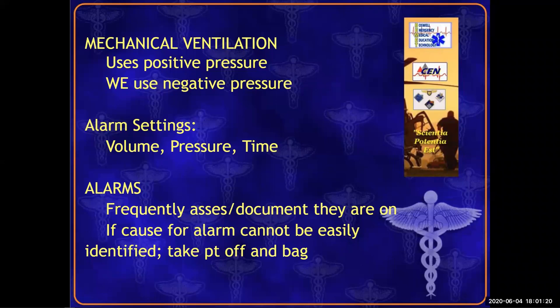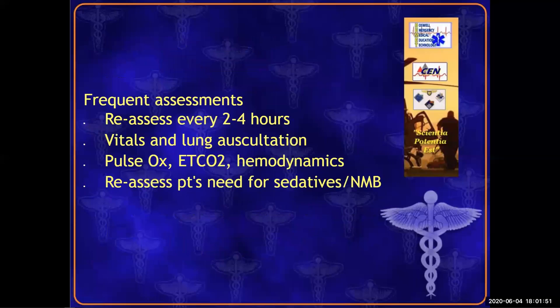It's not rocket science, but it's not something that, you know, if we're an ICU person, we do this all day long, all right? We do it infrequently enough that it's kind of a learning curve every time we have to deal with these things. All right. If you can't find the cause for the problem, get them off the machine. That's a very hard situation to defend if the machine is actually the problem and you leave a patient on a malfunctioning machine. Take them off, start doing it manually. It's going to give you a little more clues to how they're responding and so on.